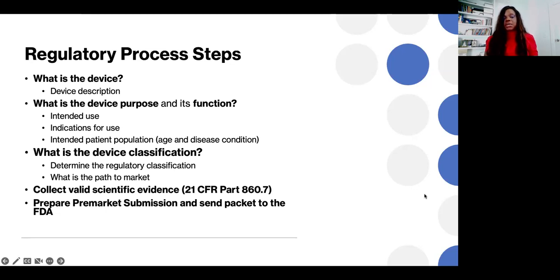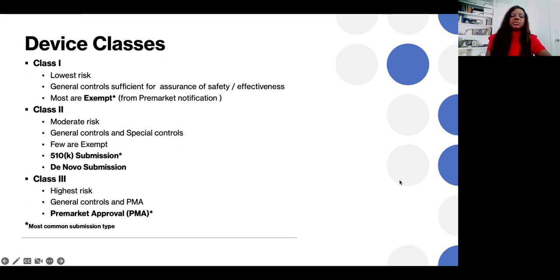In order for us to get the product on the market, we need to collect valid scientific evidence. This is described in 21 CFR part 860.7, where the FDA talks about what sort of bench or non-clinical or analytical studies we need to conduct. And then we also have to collect clinical data to support our devices. And then we have to prepare what's called a pre-market submission. And then we will send the packet to the FDA. Next slide, please. So devices are classified in 3 classes, class 1, class 2, and class 3.